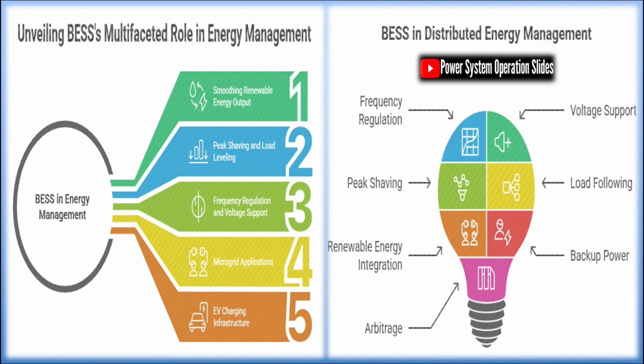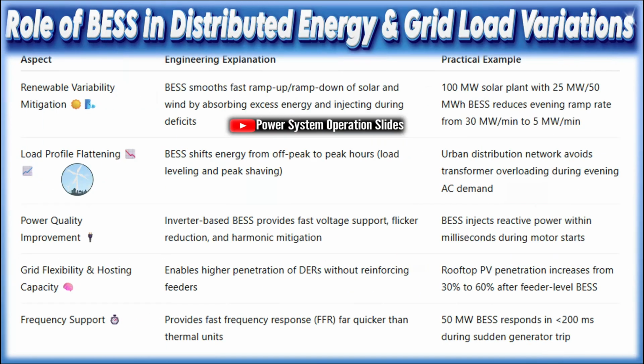Time-shifting energy, achieved through peak shaving and valley filling, allows energy to be stored during periods of low demand and discharged during peak demand periods, effectively flattening the load curve and reducing the need for peaking generation capacity. Synthetic inertia and fast frequency response, FFR, capabilities enable BESS to respond to frequency disturbances within milliseconds, providing the grid with the rapid response capabilities needed to maintain frequency stability in low inertia environments.